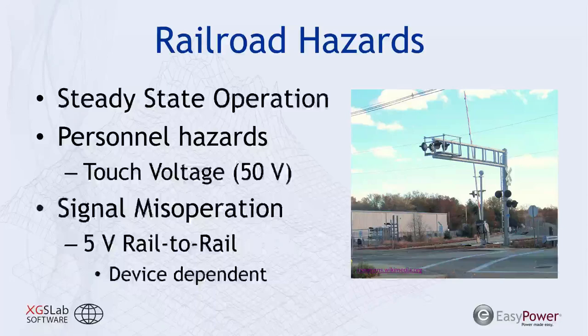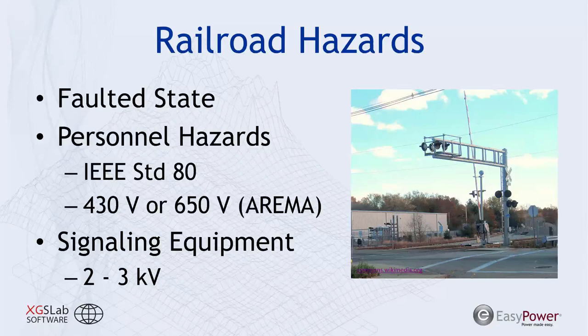Again, we have fault state concerns for railroads. Here we have, again, personal hazards that could be derived. We can derive an applicable touch voltage limit from IEEE standard 80, like we did for the pipelines, or we could reference AREMA that recommends a 430 volt or 650 volt limit, depending on the transmission line's protective systems. We also have a possibility of exceeding the signal equipment's voltage limitations, and that could cause permanent damage to the rail's signaling capabilities. And that often occurs around 2 to 3 kV. Again, that's something that you want to review on the specific device capability.